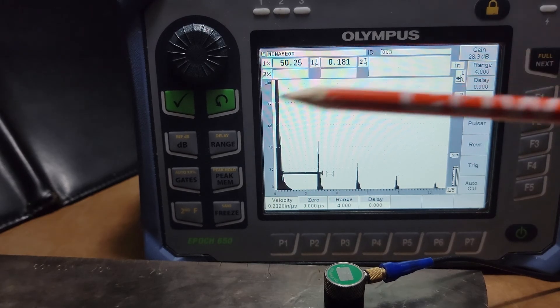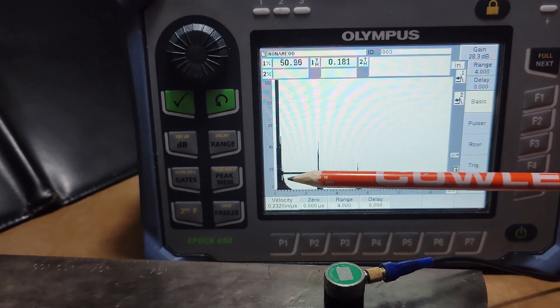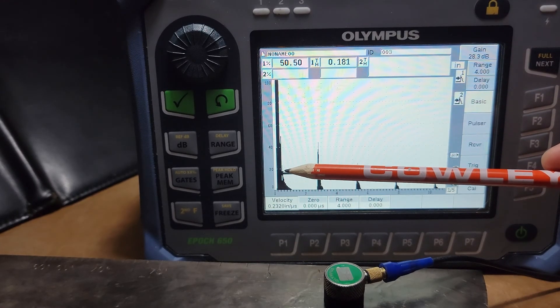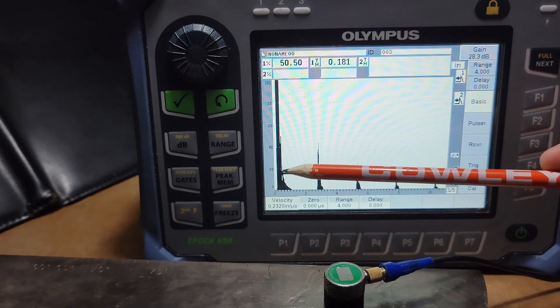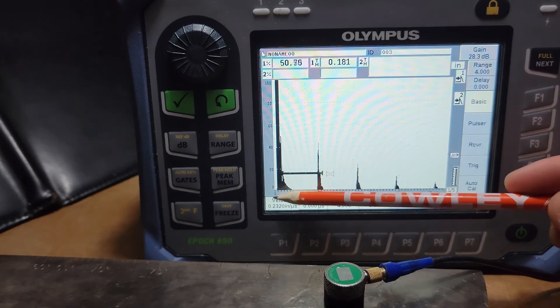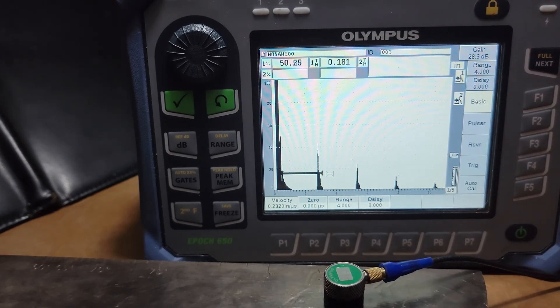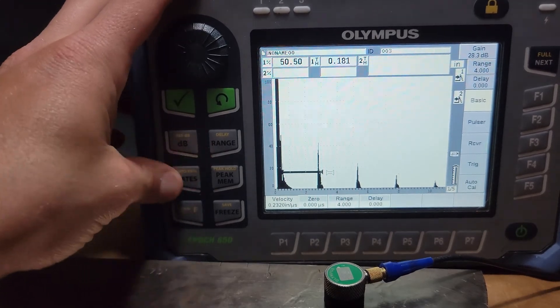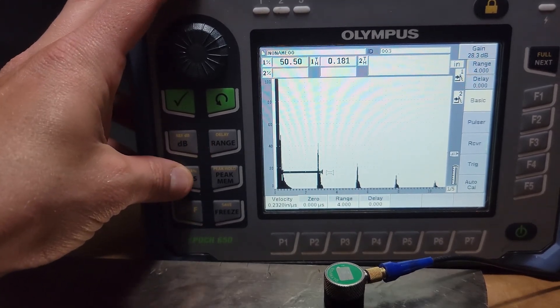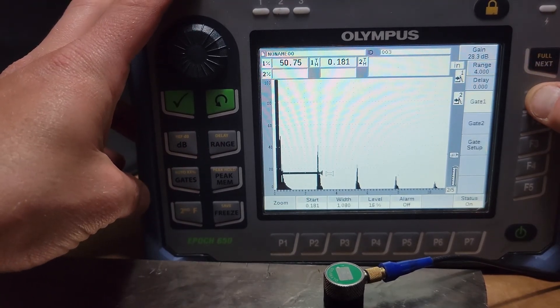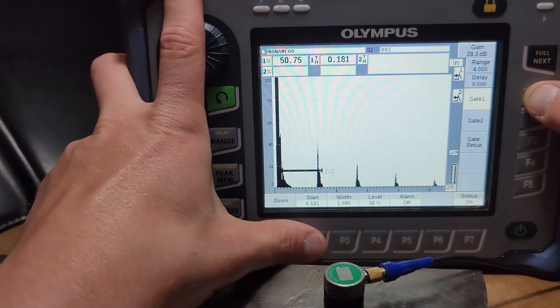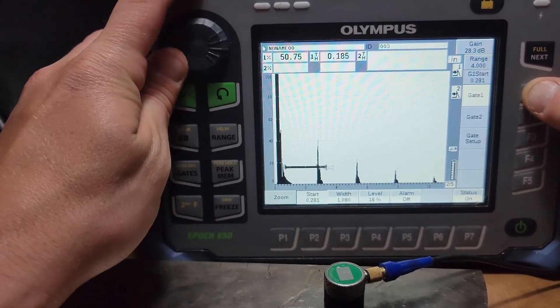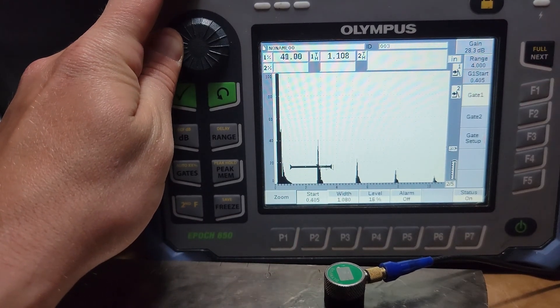Check it out, folks. Our gate is currently measuring here in that initial pulse dead zone area. So we're going to go into our first gate menu here, gate one, and we're going to grab the start position and walk it back. Hey, notice the big change here.